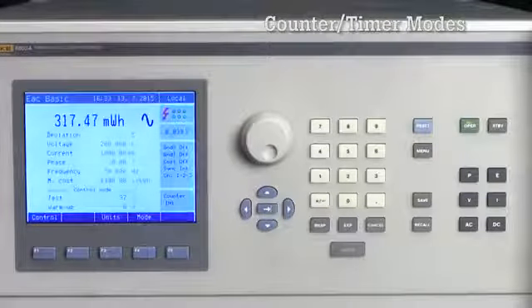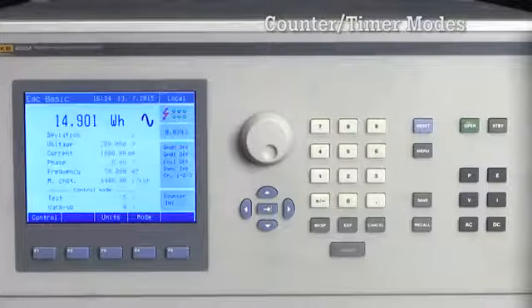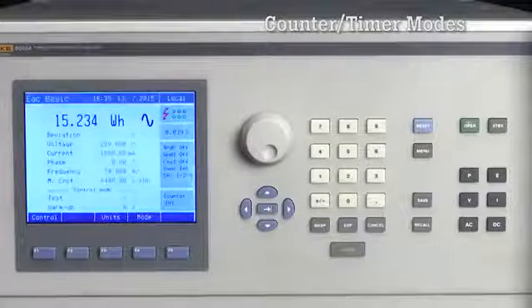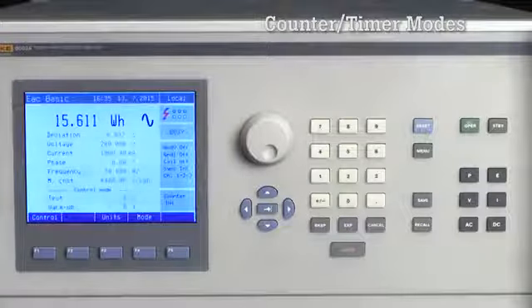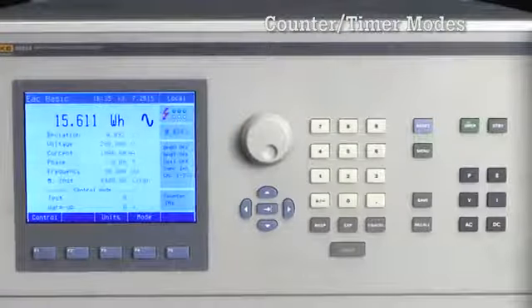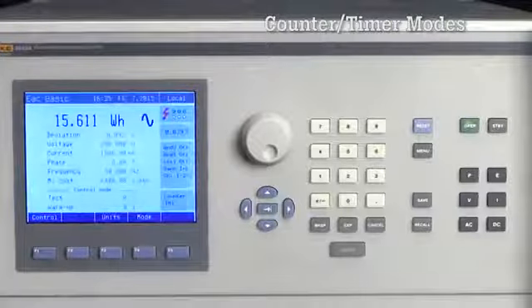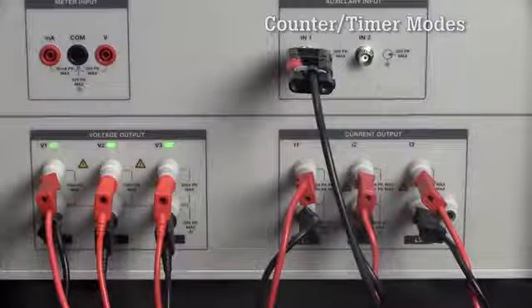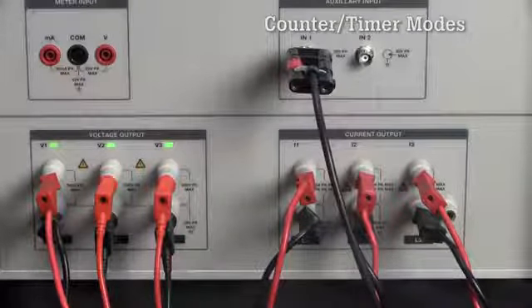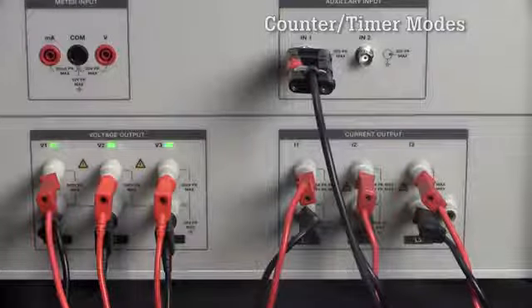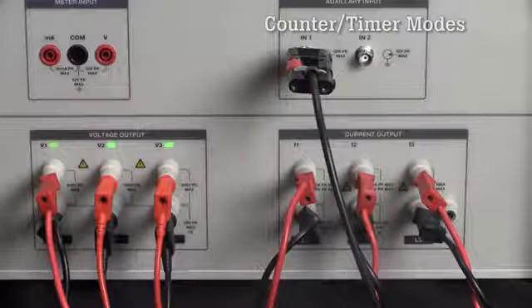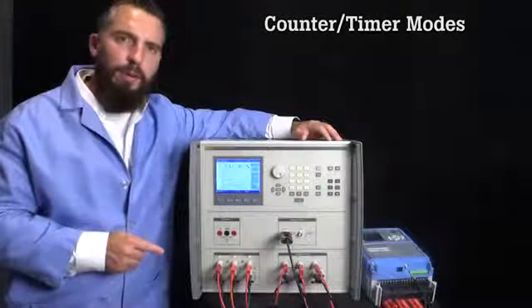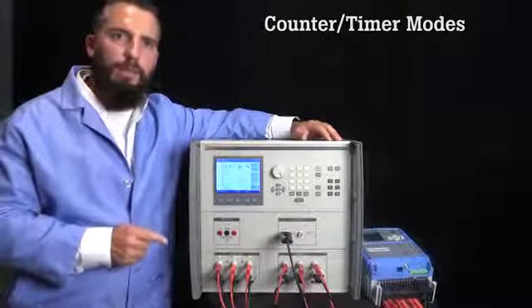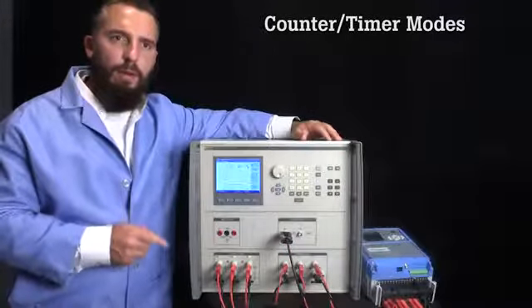Counting is finished after the set number of predetermined test pulses is reached. The display now shows energy delivered during the set number of test pulses and displays the deviation from nominal as a percentage. I would like to point out that the 6003A voltage output stayed on and the product is still in operate. This was on purpose, because many energy meters rely on the line voltage to power the meter. This is a configurable option and allows you to keep the voltage on so the meter doesn't power off.